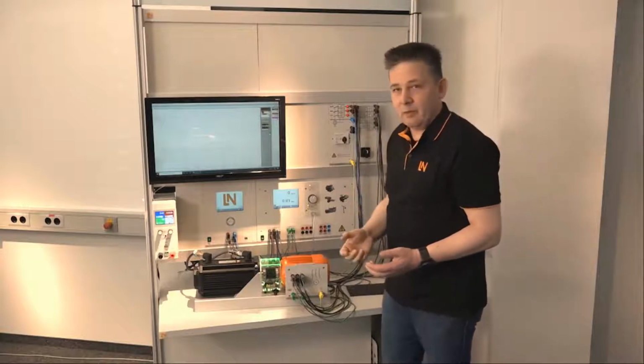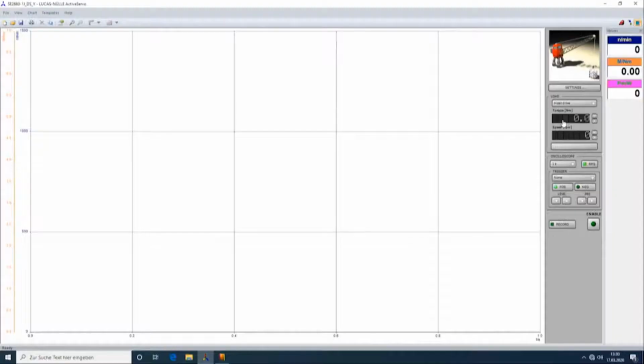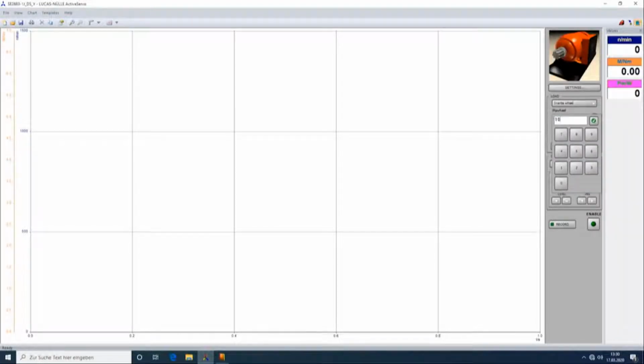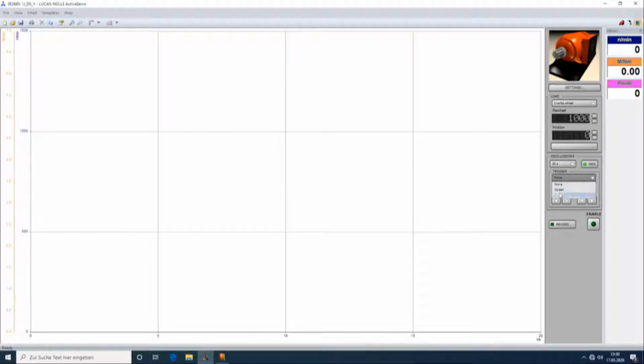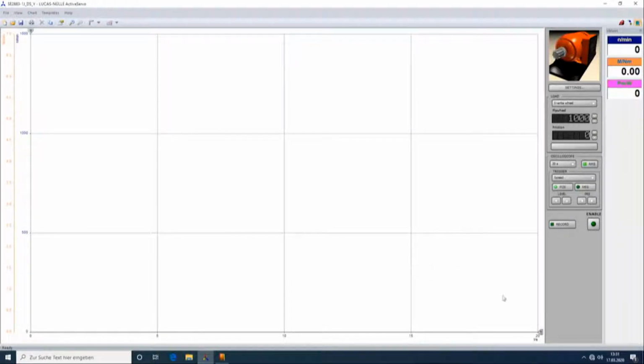But what is happening with the current inside the system? To discover the inrush current, I will choose another working machine, the inertia wheel, and then I change the flywheel to 1000 kilogram square centimeters. Now I can also adjust the axis for this. I will choose 20 seconds. For the trigger, I can choose the speed, for example, and with these small anchors, I can select the triggering point.